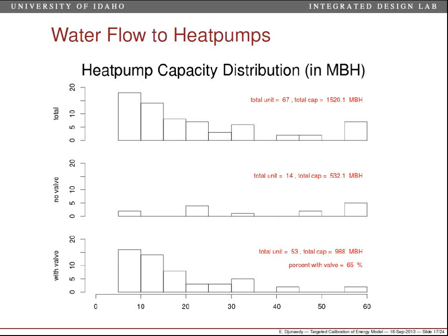Which means what? Which means that if all the heat pumps with the valve simultaneously close, no call for heating, no call for cooling, I would expect that the pump circulating the water will be working at only 35% of the capacity. Which is, I think, the lowest it can go with the VFD. Which is good. We cannot go lower than that. But the problem is, does the pump actually do that? Of course, in simulation, it does exactly that. But does it actually do it in reality?